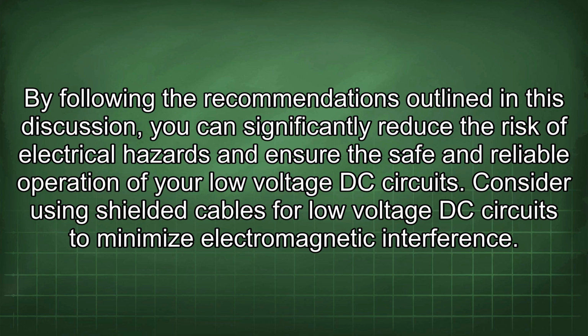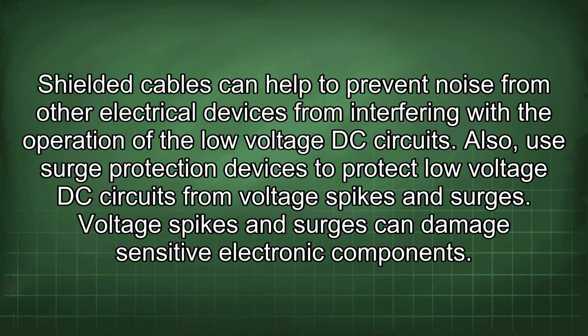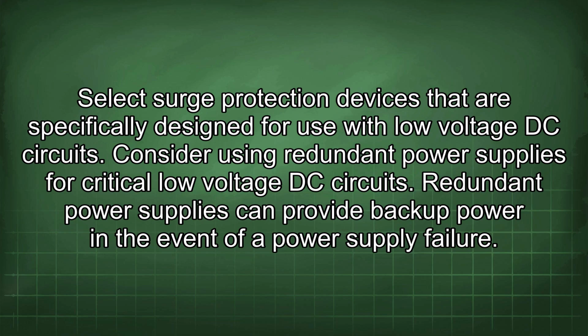Consider using shielded cables for low-voltage DC circuits to minimize electromagnetic interference. Shielded cables can help to prevent noise from other electrical devices from interfering with the operation of the low-voltage DC circuits. Also, use surge protection devices to protect low-voltage DC circuits from voltage spikes and surges. Voltage spikes and surges can damage sensitive electronic components. Select surge protection devices that are specifically designed for use with low-voltage DC circuits.